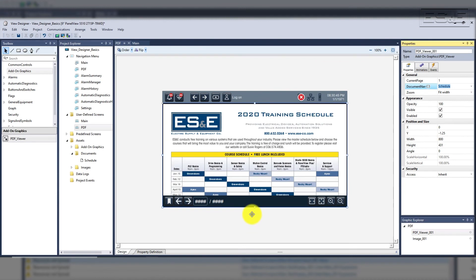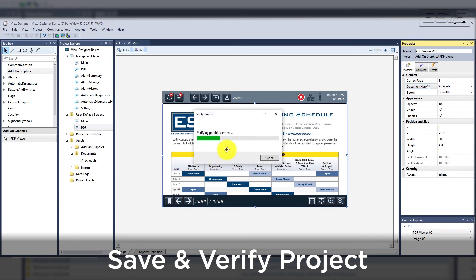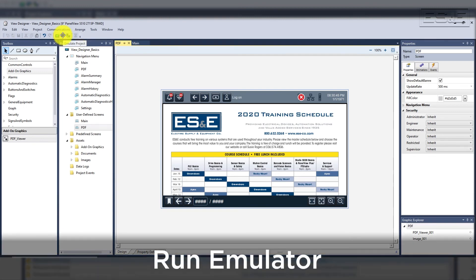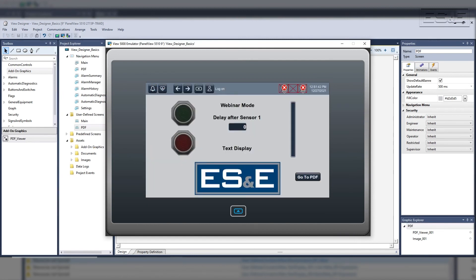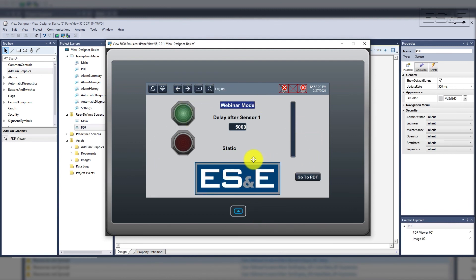Now we have finished adding all of our objects. We should save our project and then verify the project. Verifying will let us know that we do not have any errors or warnings — some examples could be having non-affiliated tags or improper tag types. Once the project is saved and verified, we can now emulate and test our screens. The emulator built into the View Designer software is an amazing tool that was well thought out and implemented. Since this project is configured for a 5510, the menu button will show in the emulator. If you have a 5310, this will not be there because it only comes on the 5510. If you select it, all the screens you had configured in the navigation menu will be shown in the pop-up window. With the emulator running, we can see live values from the PLC.